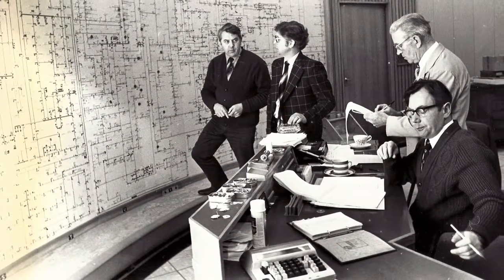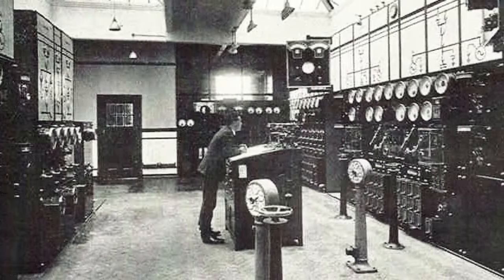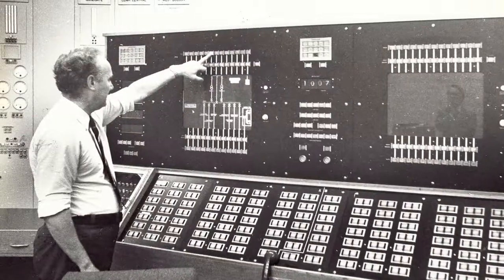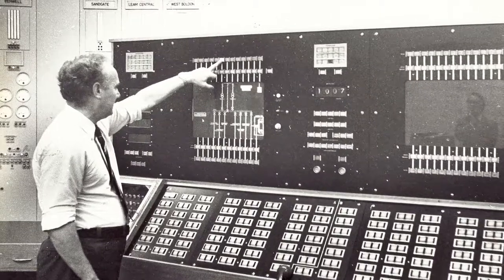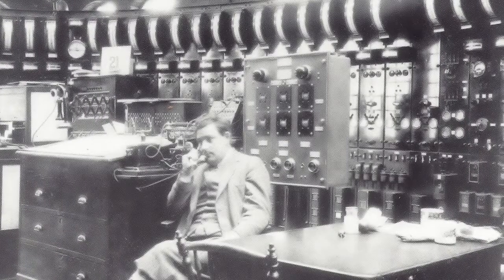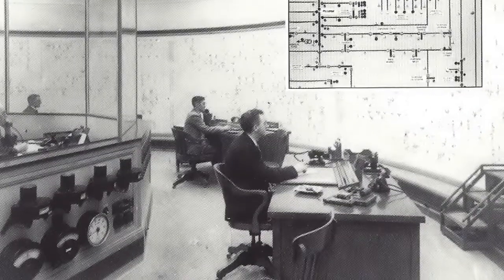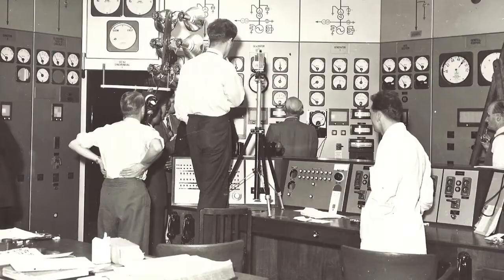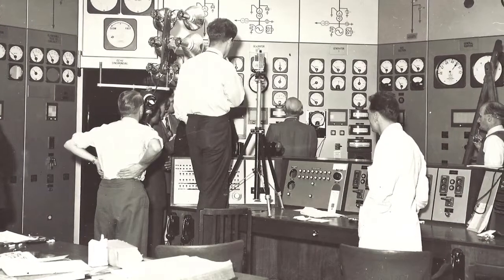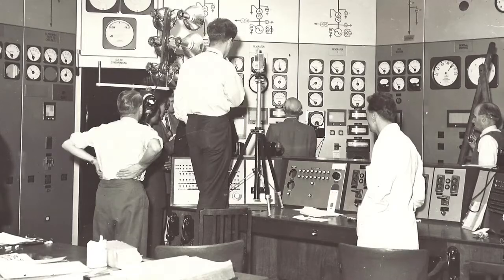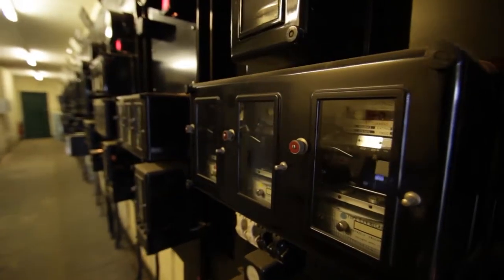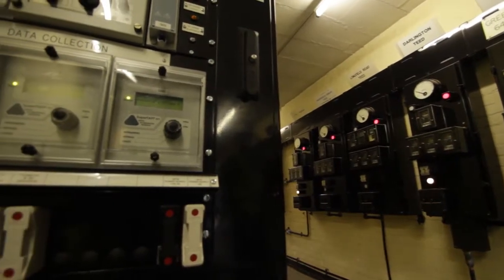We've had voltage control on the network ever since we've had a network, and automatic voltage control since we got rid of the substation attendants. A couple of generations ago, we had guys in substations manually driving transformers up and down to keep voltages at the right level. We then replaced that with a relay, a little box of tricks that did it for us. We've had automatic voltage control for so long that guys like me just grew up with it. Now we're trying to take that on a stage.